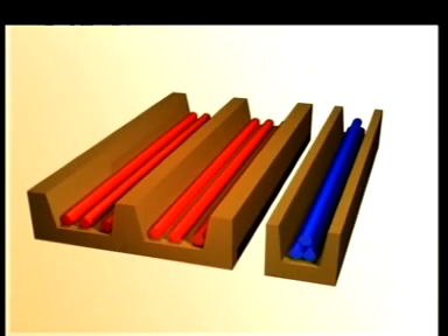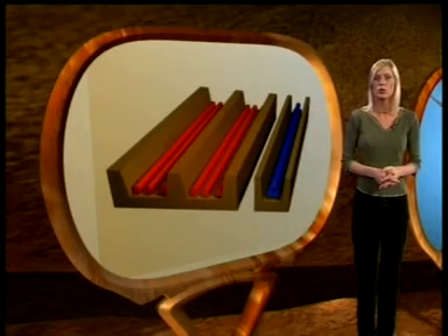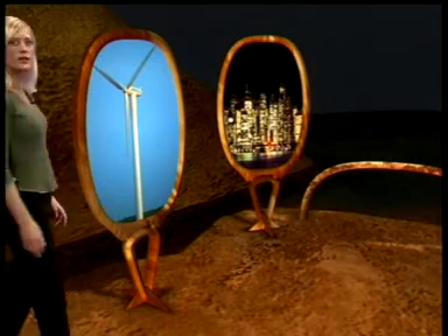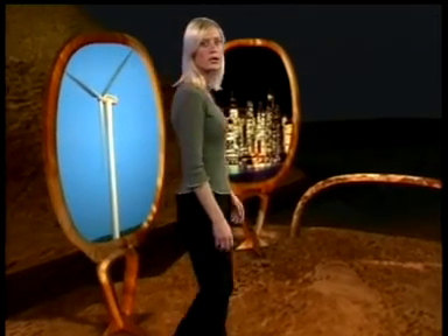These cables never get hot on the outside. This makes it possible to install cables in some soil conditions where normal cables would overheat. In many cities, it's more economical to transport electricity at the 30 to 50 kilovolt level. One example is the Copenhagen Energy's 36 kilovolt 1.8 kiloamp cable systems in central Copenhagen. Now we'll see the installation of the first HTS cable system in the public utility network.